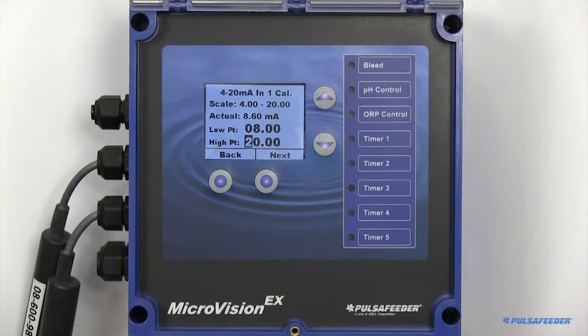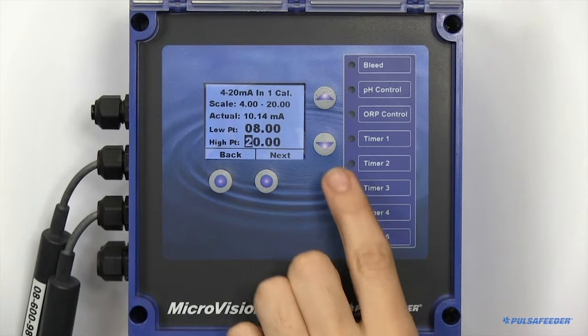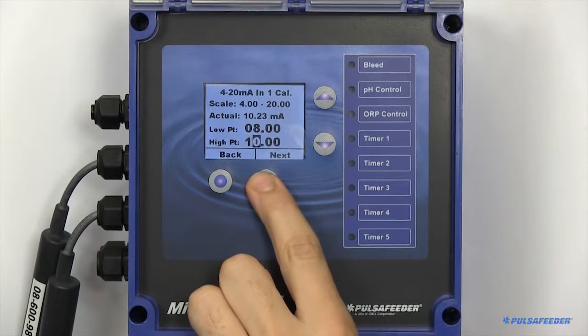Next, place your probe in your high buffer solution. Wait for your unit to adjust again. Enter the correlating value, and then enter through the bottom row. Your 4 to 20 input board should now be configured.